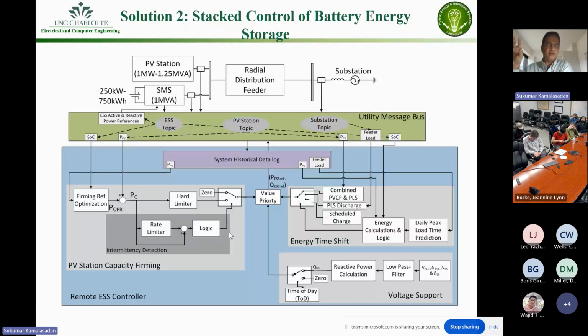So the co-located battery energy storage, grid scale, connected with a PV farm, can be utilized for support of the photovoltaics and at the same time support of the feeder associated with that photovoltaic where it is located. We tested this architecture in, it's almost 10 years old now, in the 2013-14 timeframe, field implemented with Duke, and then in the 16-17 timeframe they got it adopted onto the field, and it is currently being utilized in the field.